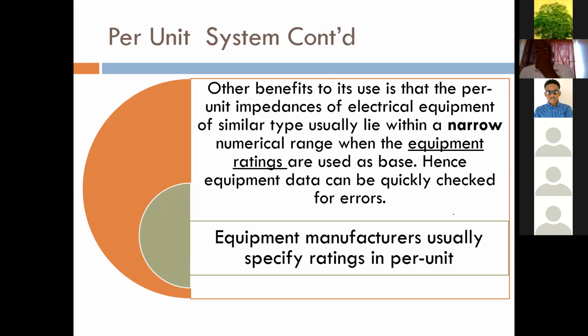So some other benefits of per unit: with practice, when you buy a transformer or work with one, the per unit value for certain types of transformer remains the same or is within a very narrow range. So you're able to quickly check for errors. If I were designing a network, or somebody designs one for me and gives me a data sheet showing a per unit value of 0.9 for the transformer, I know it's foolishness, because that is way outside of what the per unit for a transformer would be.